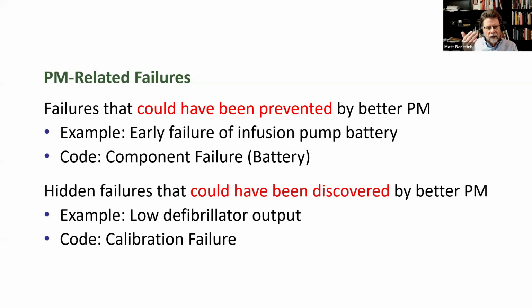So PM-related failures are of two kinds in the way we've been thinking about it. They're failures that could have been prevented by better PM, like the infusion pump battery failed early and earlier than getting to the next PM procedure. So we want to identify that with a failure code that lets you focus in your responses. It's also about hidden failures that could have been discovered by better PM, like low defibrillator output. So in that list of 14 failure code options, we wanted to identify some of those as being PM related and some of them as not PM related. And the reason is that once you've done that and standardized on that list, you can calculate not only MTBF, but mean time between failure of PM related failures.